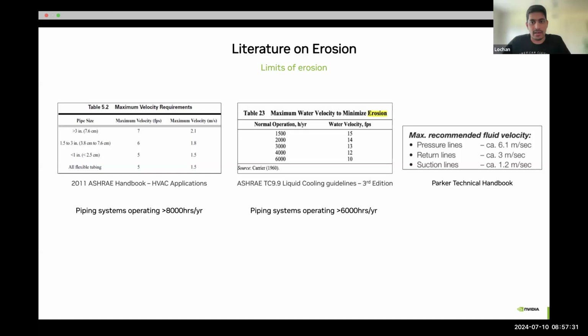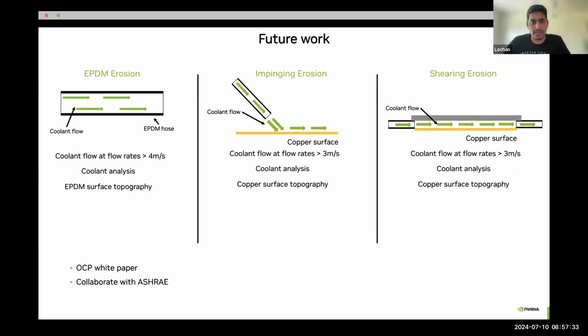So based on these current guidelines, we are looking into three different studies. The first one will be the EPDM erosion, where we'll be going more than 4 to 5 meters per second. Currently, our goal is to go over 6.5 meters per second to see if we can see any erosion of the EPDM internal surfaces at high flow rates and high temperatures. We'll be looking into the EPDM surface topography, and also the coolant analysis to see if we can find any eroded particles of the surface.